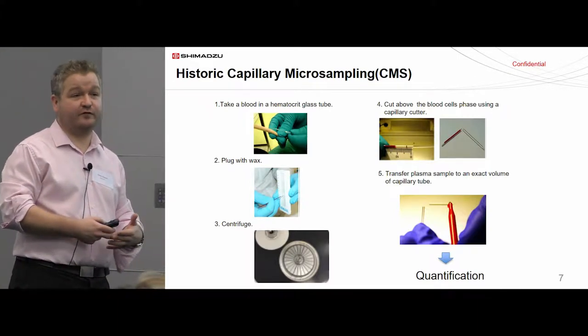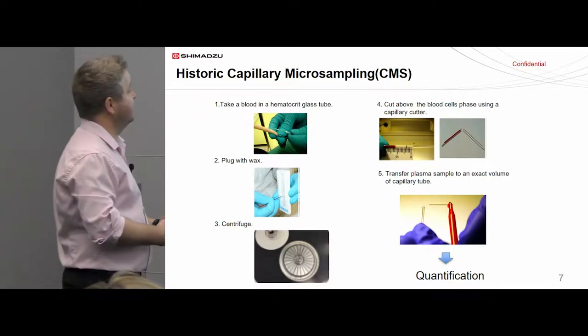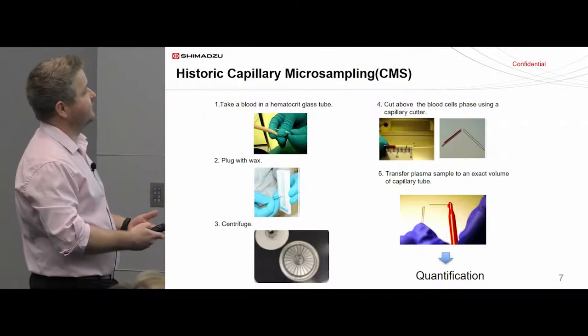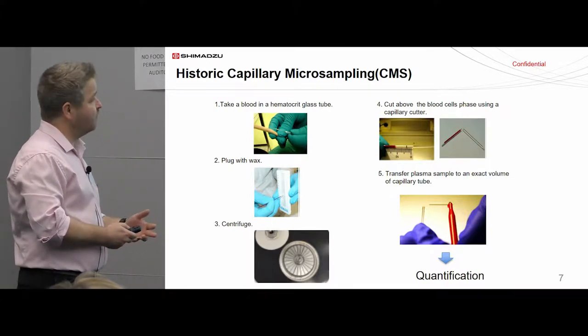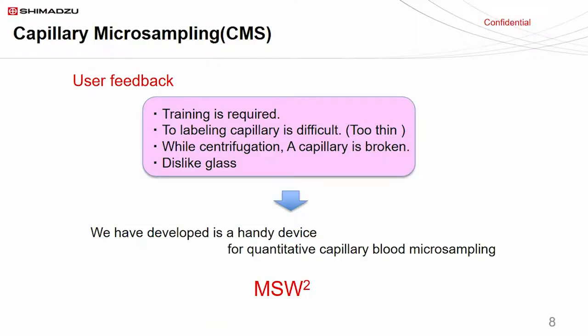The microsampling wing replaces historic capillary microsampling, where we take a hematocrit glass tube, plug it with wax after taking the sample, centrifuge, snap the tube, and take this aliquot of plasma for quantitation. Feedback from end users showed that training was required with a lot of variability depending on how you were trained. Labelling of the capillary is incredibly difficult because the tubes are very thin, things are often broken while centrifuging, and there was a general dislike for glass — though I only found out today that plastic alternatives are available.